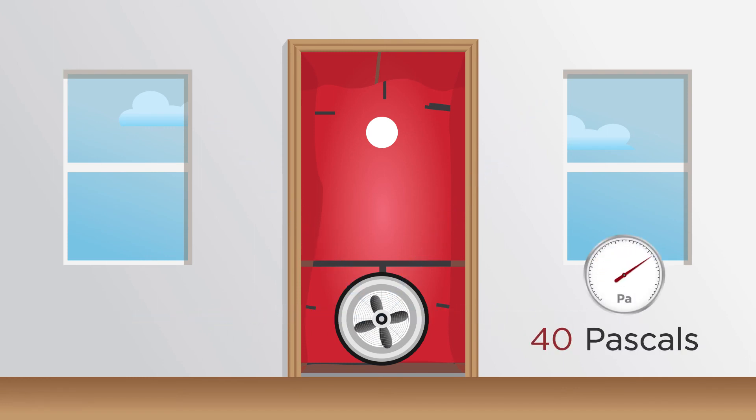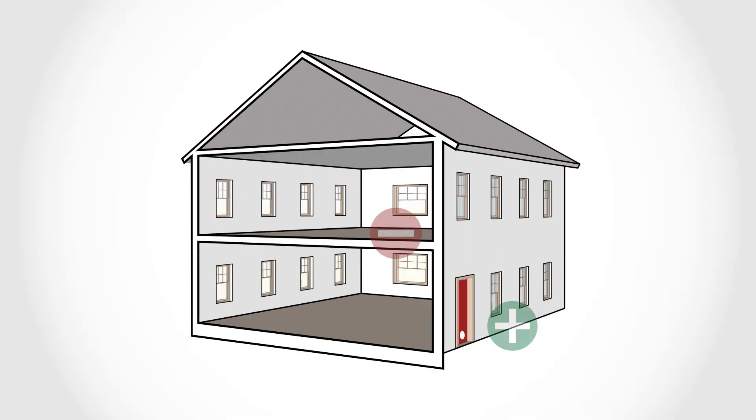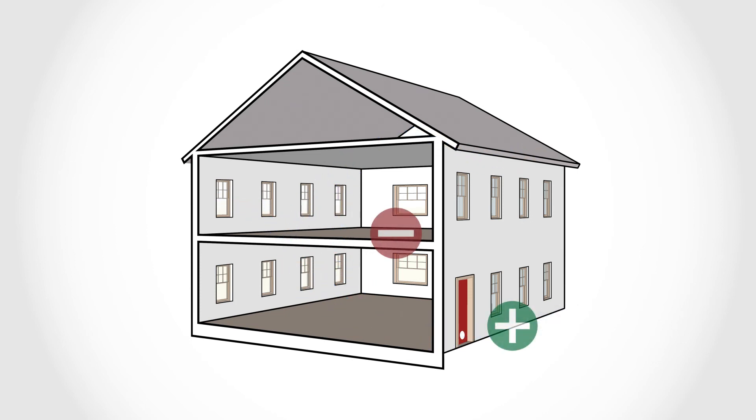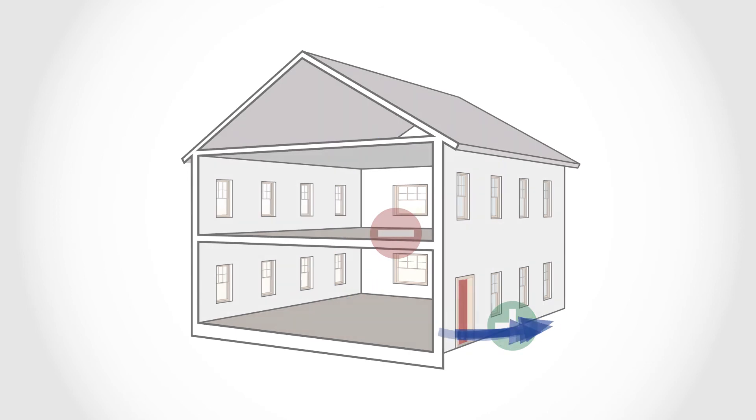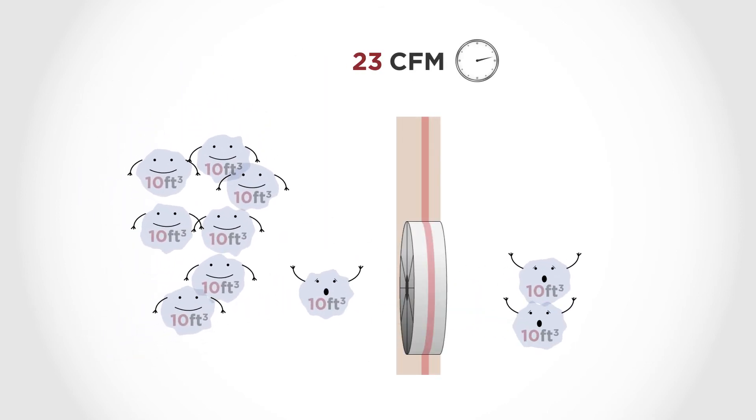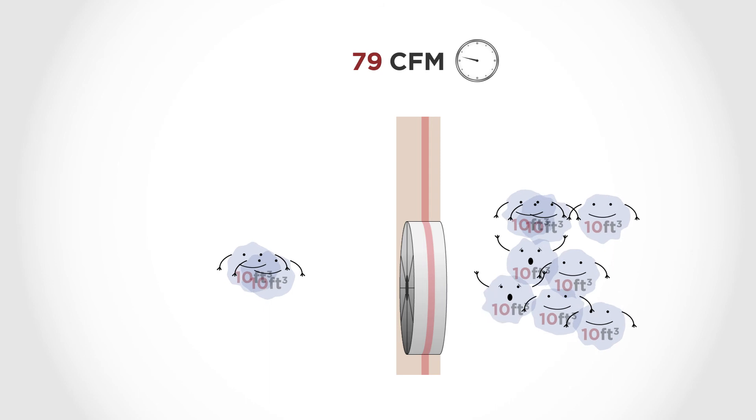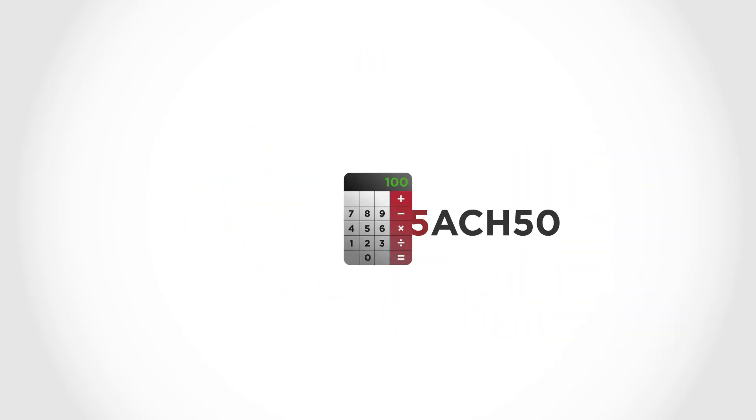The pressure difference created by the fan pulls air in through all the leaks, cracks, gaps, and penetrations in the house. The amount of infiltrating air is equal to the amount of air flowing through the fan, called the flow rate, which is expressed in cubic feet per minute and converted to air changes per hour.